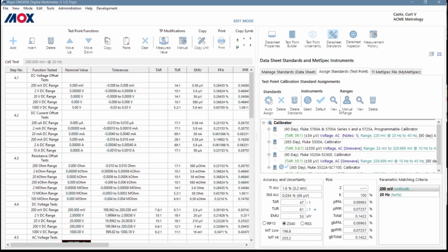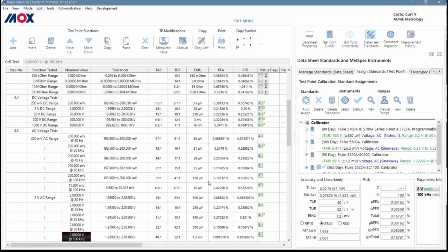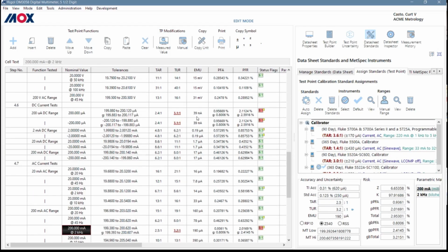Just by using this software, they're going to start to learn that there's something they need to be paying attention to. I've run into it for many years in my career, where they're just not even aware of it because the system's not designed to make sure they're aware of it. You're relying on your metrologist to tell you. Having that visual right there, being able to see your TURs, a lot of the time some techs don't know, hey, I need to use a different current meter for this, or something that's ranged down a little bit more. They may be doing it wrong for years.